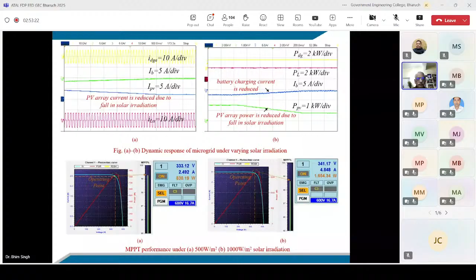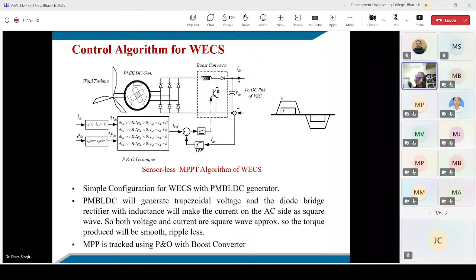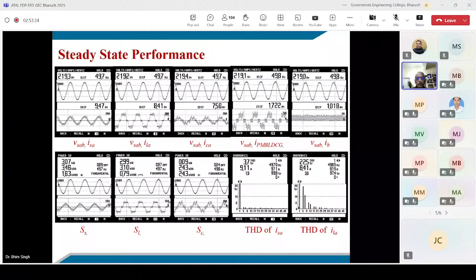Another case we worked out was with wind along with the DG set and with the battery connected, and that was again controlled properly with the DG set. We worked out maximum power tracking successfully with the DG set also, not only with the grid as is typical. We are able to get low THD even under non-linear load, and we worked under wind variation, load variation, and motor starting. You can see how the induction motor is started and how the battery current is quickly taken through the converter, so the converter current increases a little bit. But the voltage is not affected. The terminal voltage remains constant, and there is no dip. So this was an interesting control.